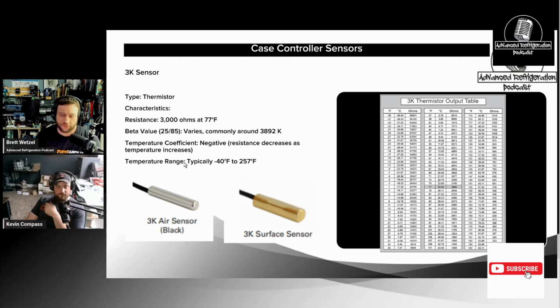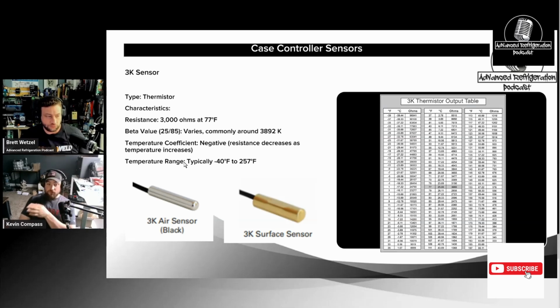But with sensors, there's not that much to check. You see what it is right at the system itself. Side note, I'll say this: make sure your meter reads a high enough ohm reading. Not all Fluke meters will read over 10,000 ohms. A lot of their HVAC meters - I think the 116 may, but the 902, the FCs, the clamp ones - generally do not read over 10,000 ohms. So if you're trying to check sensors, that meter may not read over that.